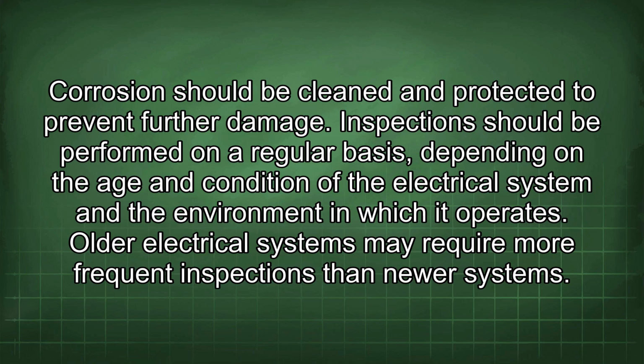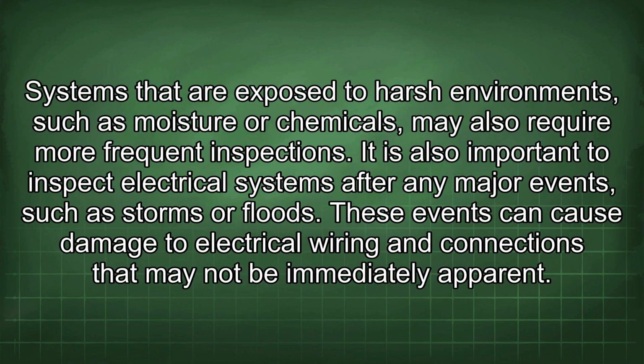Inspections should be performed on a regular basis depending on the age and condition of the electrical system and the environment in which it operates. Older electrical systems may require more frequent inspections than newer systems. Systems that are exposed to harsher environments such as moisture or chemicals may also require more frequent inspections. It is also important to inspect electrical systems after any major events such as storms or floods. These events can cause damage to electrical wiring and connections that may not be immediately apparent.